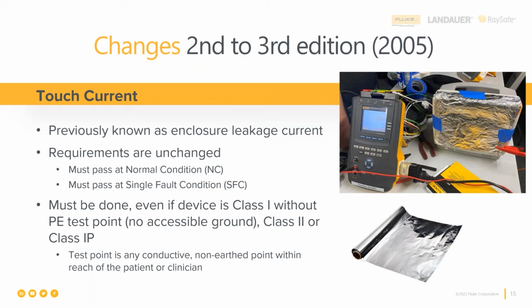This test must be done to a conductive test point, not grounded or earthed, within reach of the patient or the clinician. That means you have to move your test lead away from the protective earth or ground test point to this other conductive but not grounded test point where the patient could touch it.